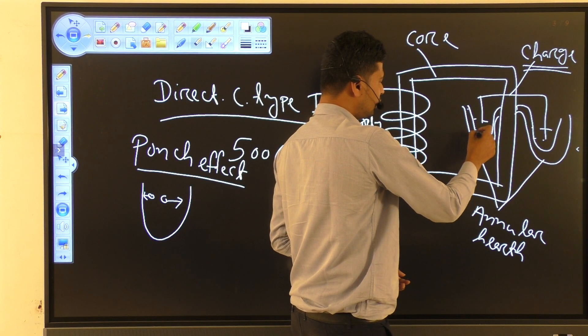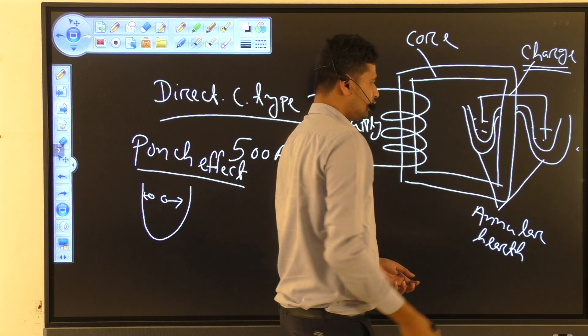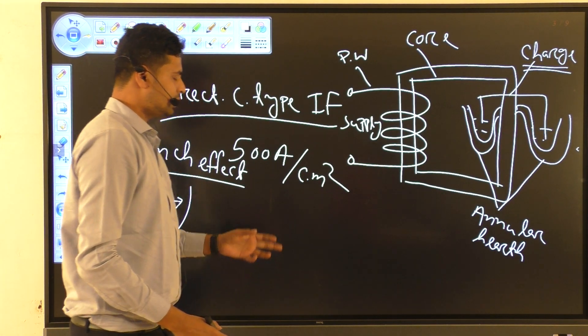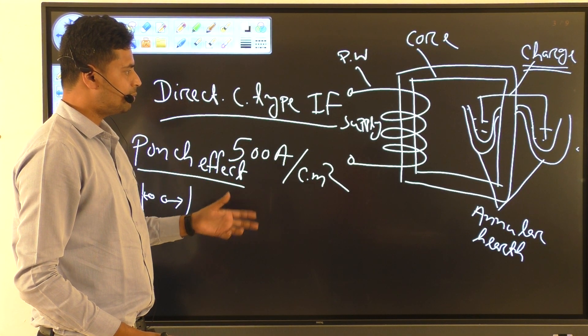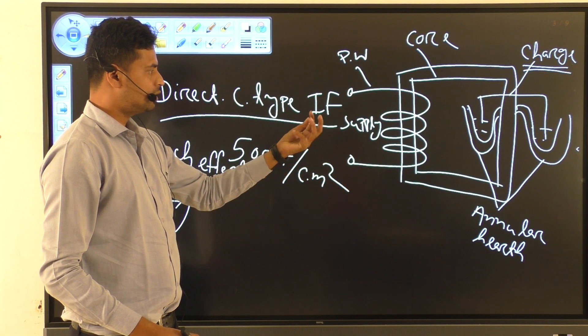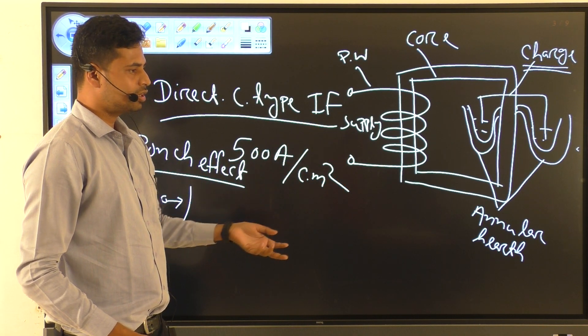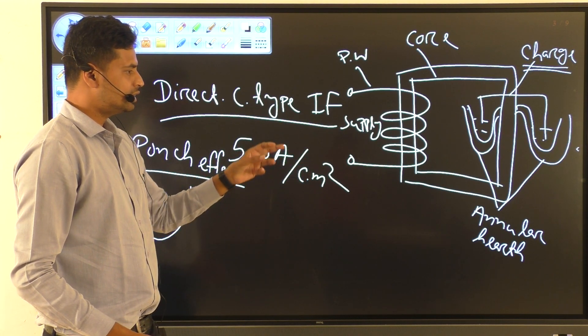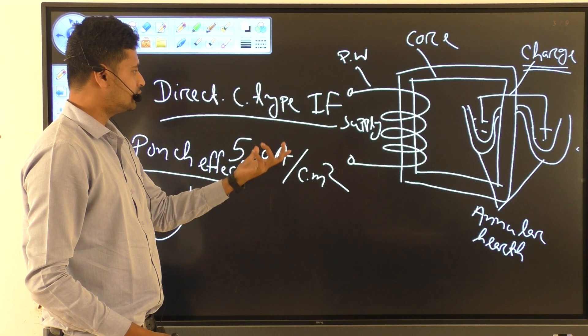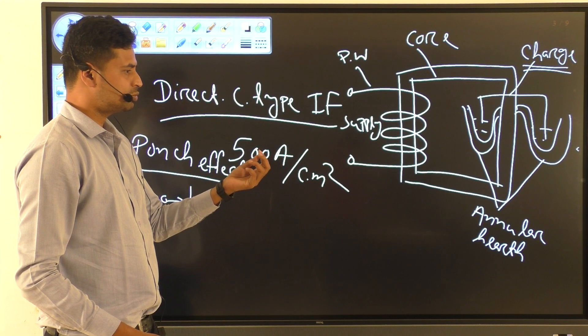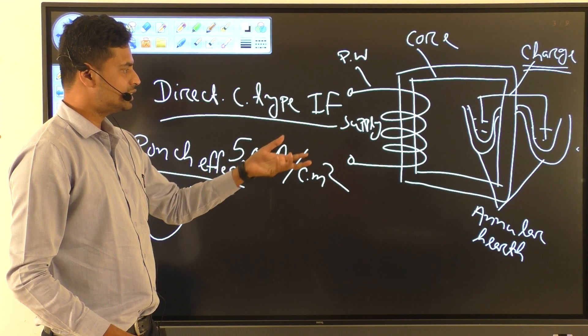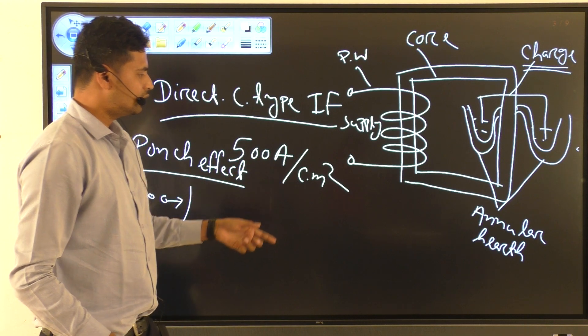In the annular hearth, the charge is melted. The first demerit of the direct core type induction furnace is that it cannot be operated without first pouring a small amount of molten metal or molten charge. This small amount of molten material is needed to create a short circuit so that the furnace can start. Without it, it cannot be started.